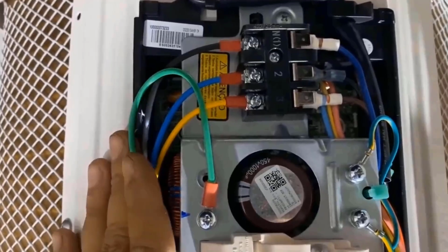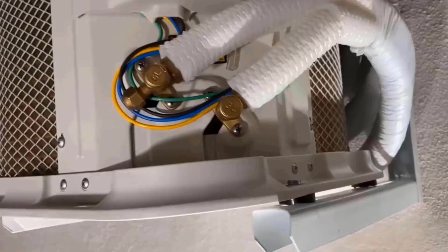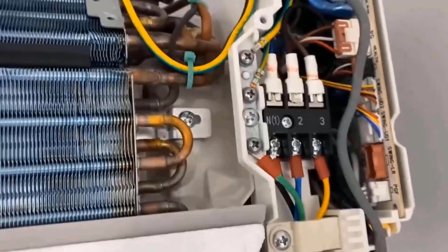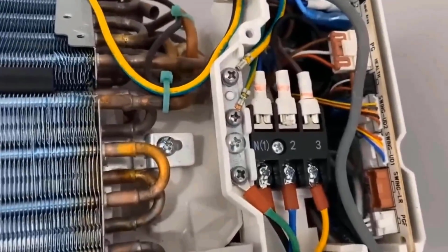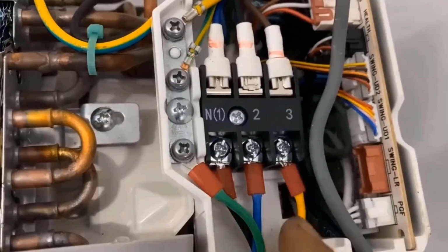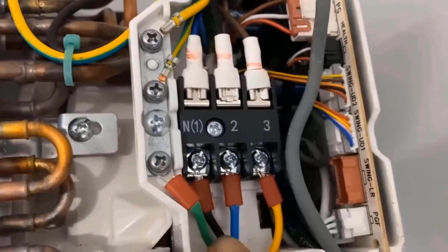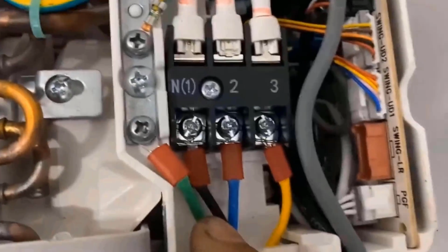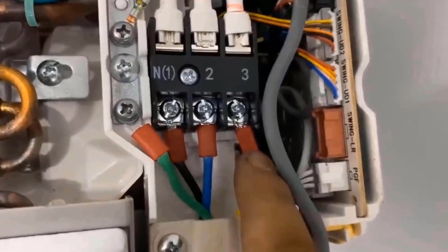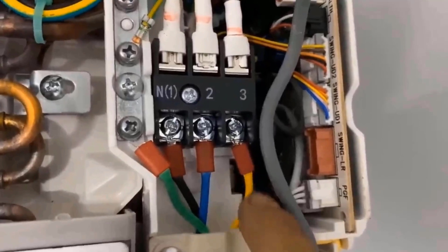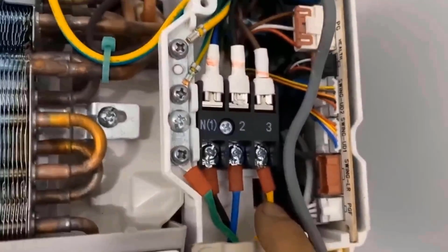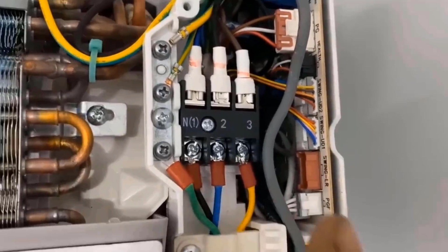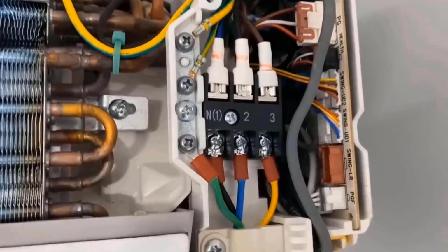Now imagine that the equipment has been in operation for some time and the error appeared. If the user is not a technician and encounters this problem, what can he do? If the equipment was installed correctly and the error appeared later, there may have been a problem. It could be on the control PCB, which may have been damaged or is being interfered with, but in any case, the error will be related to the main board. Another possibility is a broken wire or even oxidation, which can occur if rainwater has gotten in, for example.